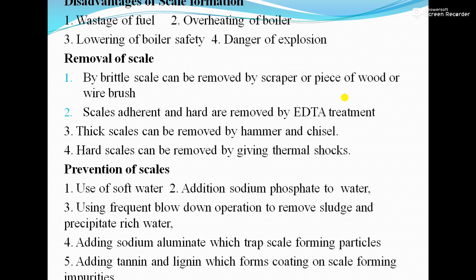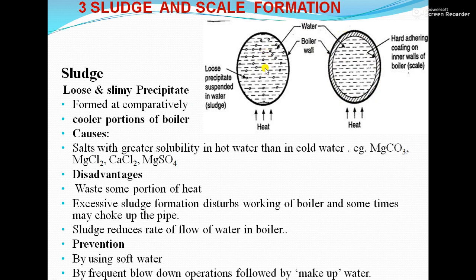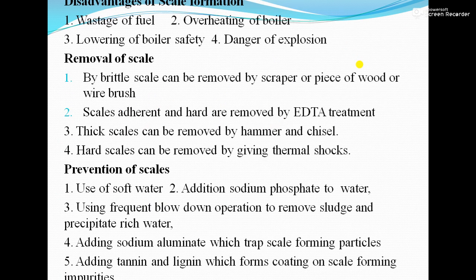Preventions for scale formation: first, use soft water; second, add sodium phosphate to the water; third, frequent blow down operation to remove sludge and precipitate-rich water; fourth, addition of sodium aluminate which traps scale-forming particles; fifth, addition of tannin and lignin which form a coating on scale-forming impurities, keeping them suspended in water so they can be removed by blow down operation.